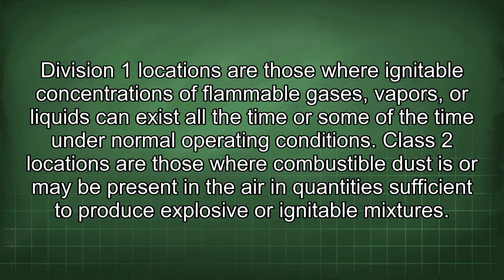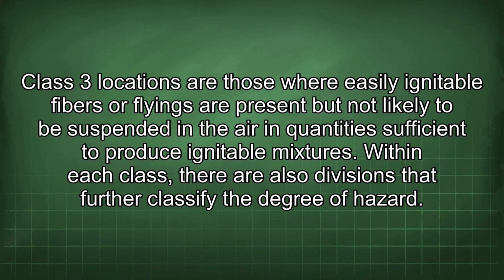Division 1 locations are those where ignitable concentrations of flammable gases, vapors, or liquids can exist all the time or some of the time under normal operating conditions. Class 2 locations are those where combustible dust is or may be present in the air in quantities sufficient to produce explosive or ignitable mixtures. Class 3 locations are those where easily ignitable fibers or flyings are present but not likely to be suspended in the air in quantities sufficient to produce ignitable mixtures.